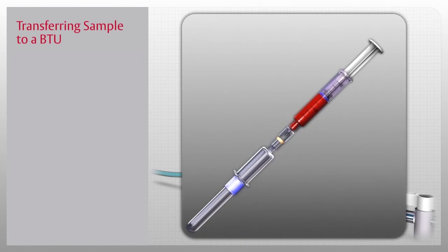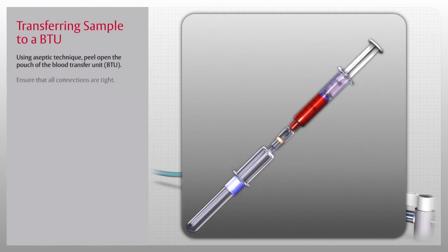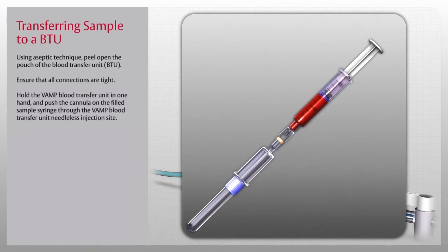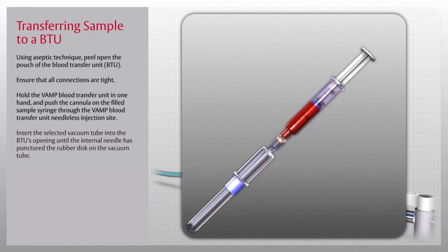To transfer the blood sample from the syringe to vacuum tubes, use the blood transfer unit, or BTU. Using aseptic technique, peel open the pouch. Ensure that all connections are tight. Hold the VAMP blood transfer unit in one hand and push the cannula on the filled sample syringe through the VAMP blood transfer unit needleless injection site. Insert the selected vacuum tube into the BTU's opening until the internal needle has punctured the rubber disc on the vacuum tube.